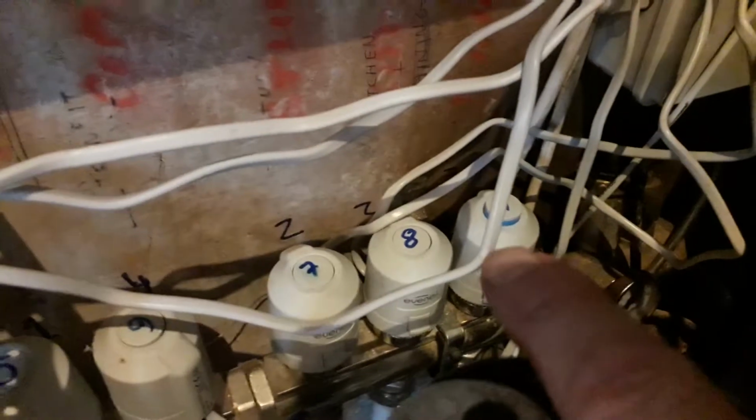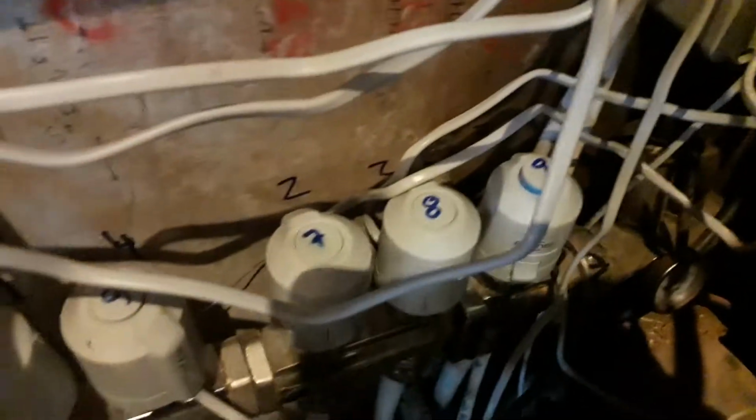So we don't know now whether the label is incorrect or whether somebody has moved it from what should be the study. So what we need to do is switch on one of these loops at a time while all the others are off. We know it's on by the blue ring being up, and I've tested it earlier, so we are getting flow. We've got heating in the pipes on the flow going into the underfloor. So we would turn it on just as we have now, and it's going to take some hours for each part of the floor in the house to react.